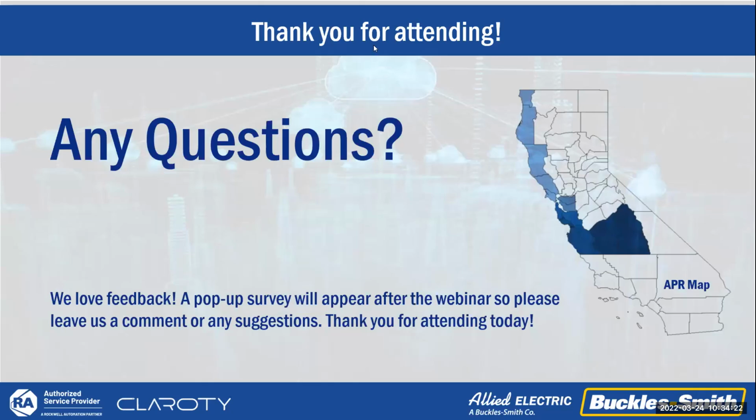This is Chris. Okay. Yeah, there's a few things. I mentioned unmanaged switches. So there's no port security on unmanaged switches. That means that anybody with an Ethernet port and a cable can come in and plug into your network. Whereas in a managed switch, you can actually block those ports off, or actually with our Stratix switches, you can have your control system need to log into the control system that will enable a port for you.